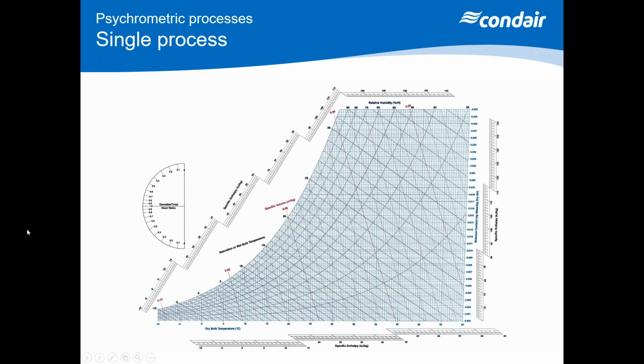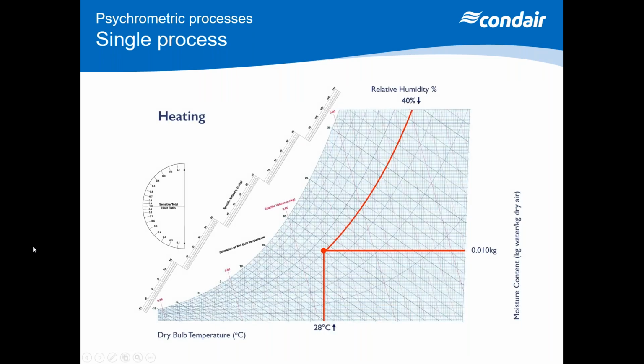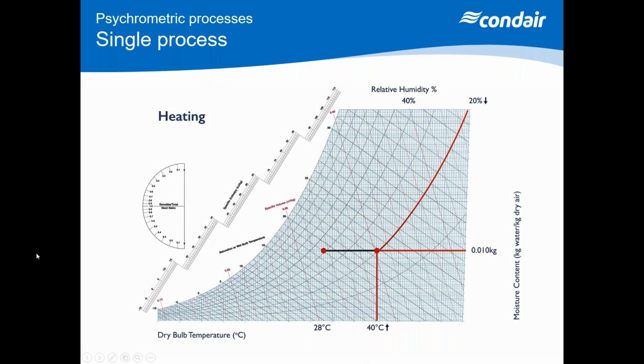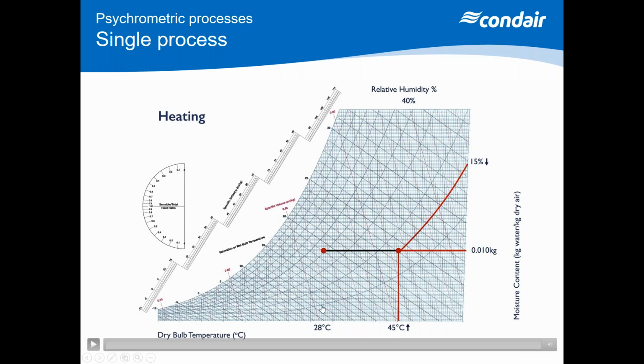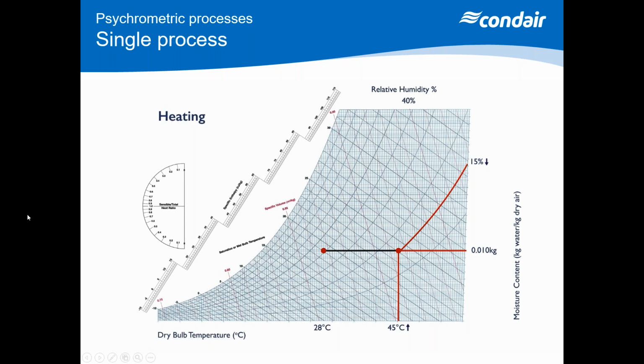So what do we do with it? Okay, well, the great thing about it is we can draw a process on the psychrometric chart and find out what happens to the air when we do that. So let's say we're going to heat the air up just by dry sensible heating. So if we apply sensible heat to the air, we're going to see a process similar to this, where we see an increase in dry bulb temperature. We see a decrease in relative humidity, though. There's 40, 30, 20% RH. But we haven't taken any moisture out, or indeed put any moisture in. So the absolute humidity will remain the same. So that's our heating process line.